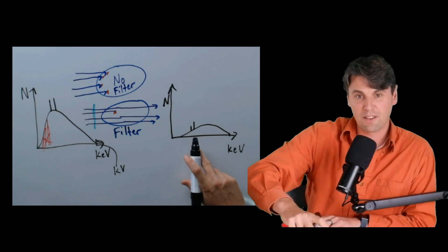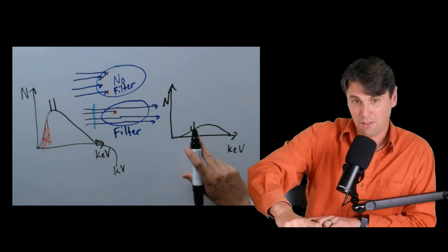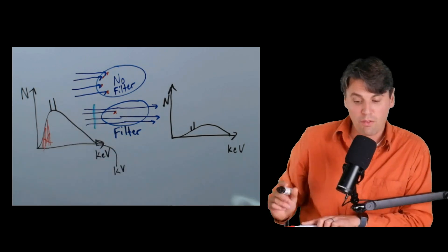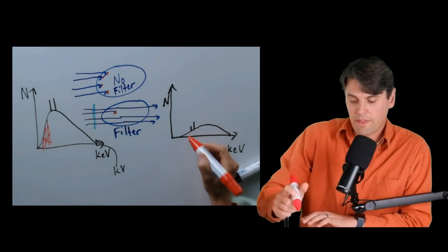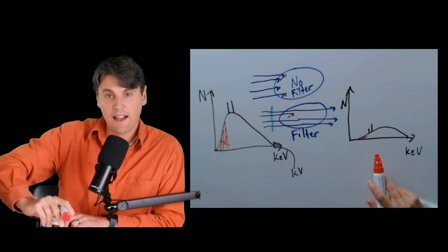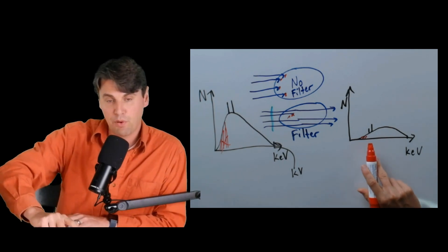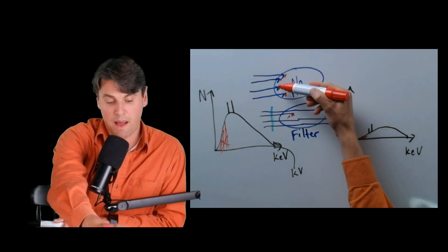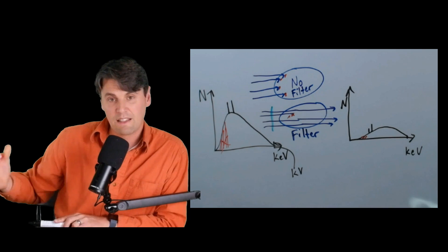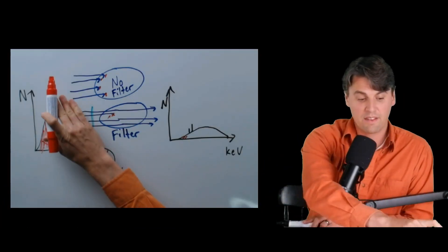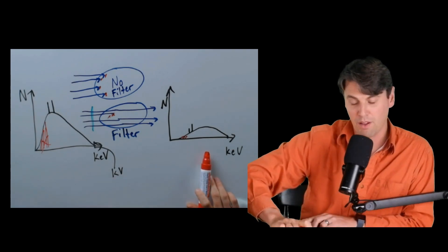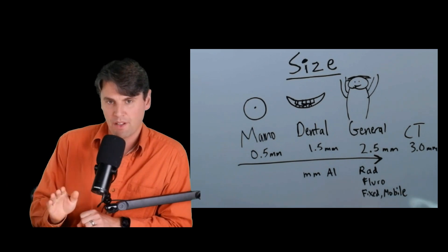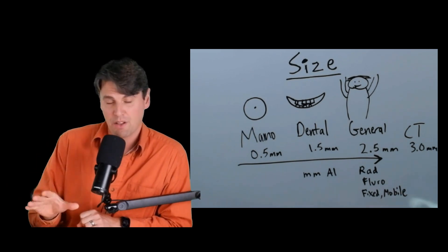Those little peaks in the spectrum are what we call characteristic x-rays — see our video on characteristic x-rays and x-ray production if you need a refresher. The whole hump is due to Bremsstrahlung radiation. After filtration, there are still a few lower energy x-ray photons in the beam, but we've significantly reduced them. We're no longer depositing as much dose near the surface that has no chance of reaching the image receptor. For patient safety, the NCRP has defined minimum filtration limits that depend on the size of the patient and type of acquisition.